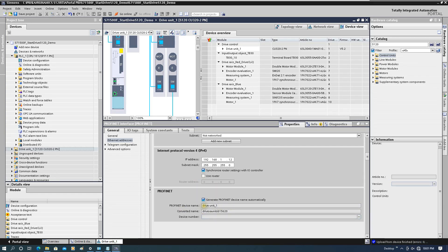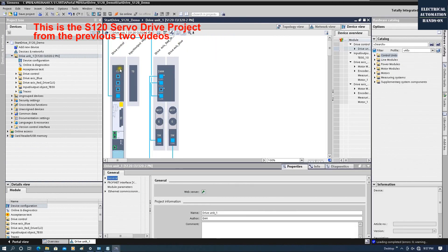I prefer this way because in most cases — especially for bigger projects — the PLC programming and drive commissioning usually have two main programmers. Using this approach, the drive programmer can mainly focus on the drive first. Then after the PLC programmer is ready, they can create the PLC project and upload all the existing drive configuration into the final combined PLC and servo drive project. In this video, I will mainly show this method. Before we start configuring the PLC project and station, we first need to go online and double-check the current firmware version of the S120 CU.